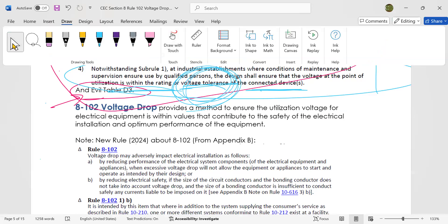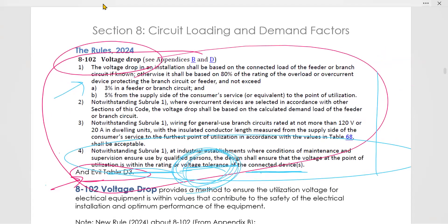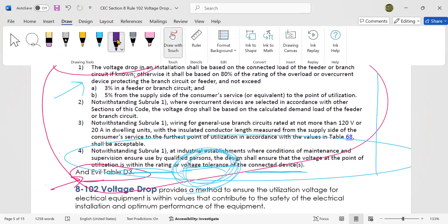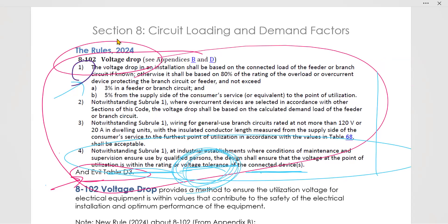All I did in this video is I walked you through subsection 1, 2, 3, and 4. And as a summary, subsection 1 says that you can't drop from supply to service, sorry, from supply of the service to the point of utilization. You can't drop more than 5% and you can't drop more than 3% in any feeder or branch circuit.